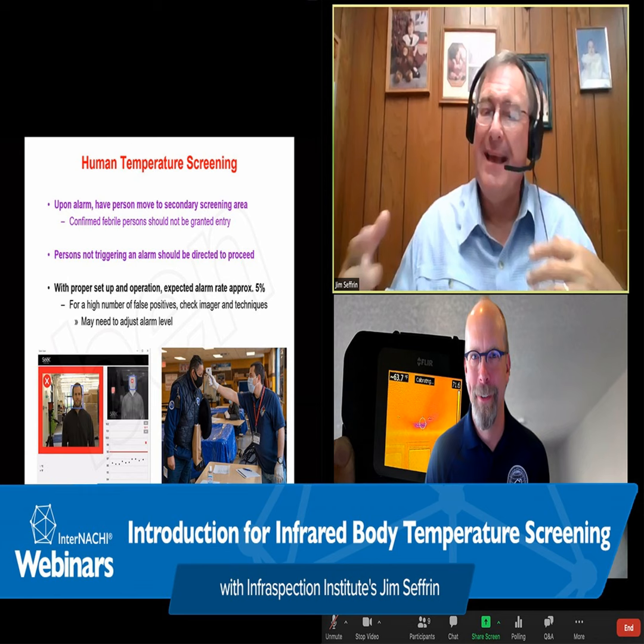When you have someone that indicates a positive result with the thermal imager, we then use a secondary tool. In this case, pictured here, we see a medical grade infrared thermometer to confirm the presence of a fever. We can also use this if we are operating a screening checkpoint at the entrance to a school or facility. We can also use that thermometer for periodic confirmation that the imager is working properly. So if persons are passing through and you're getting a reading of 98, 97, 97.5, and your independent confirming thermometer is confirming those numbers, then you have agreement and it confirms that you're doing things properly.